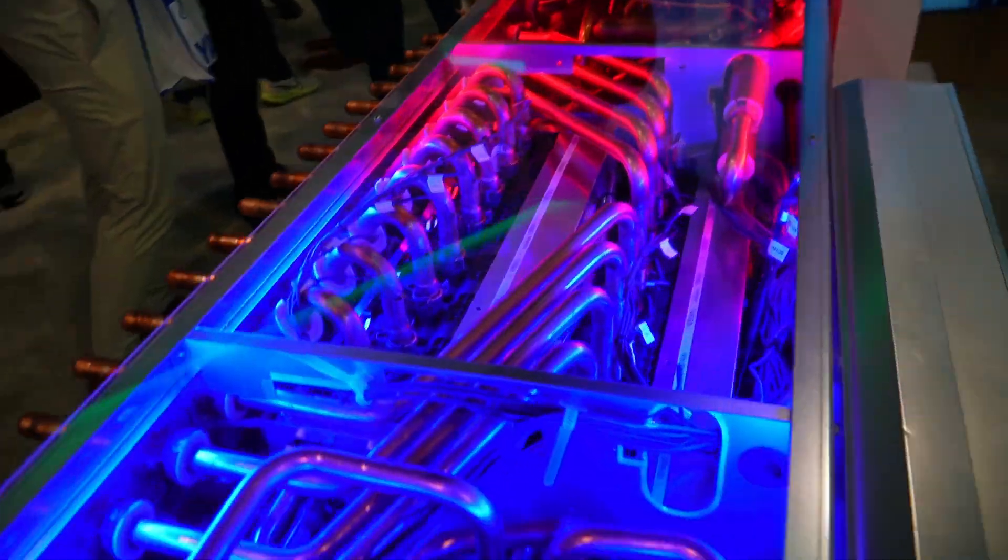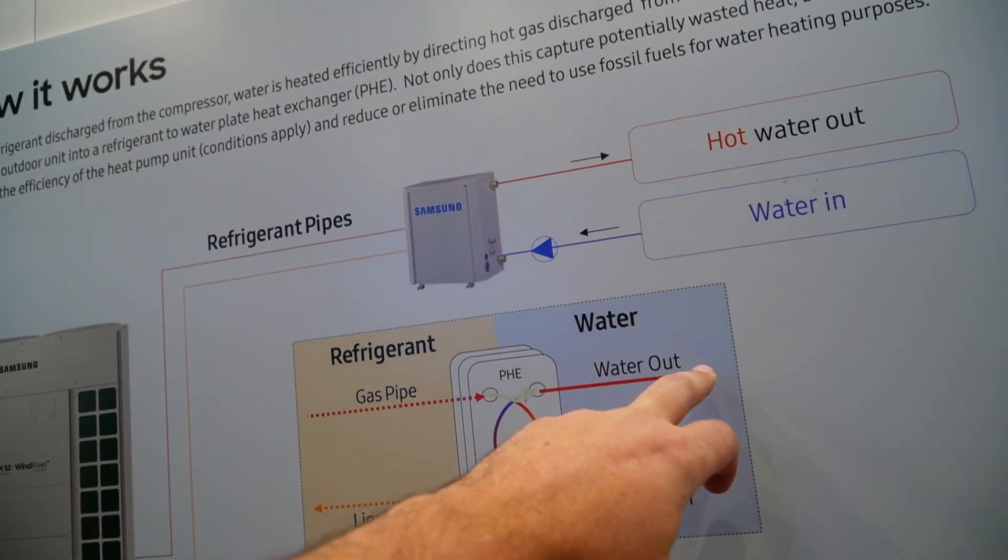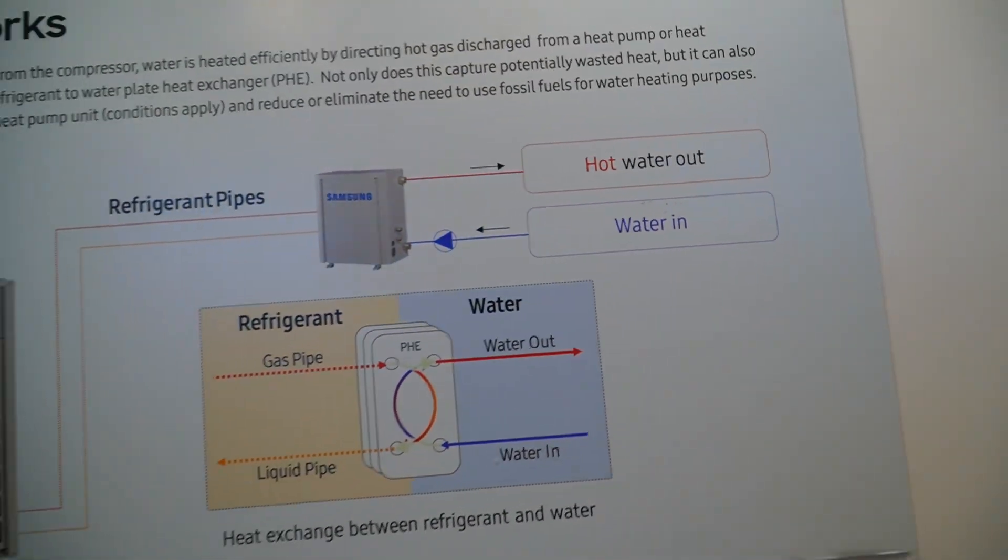This isn't just a regular branch selector — this is actually quite fascinating. They have integrated the hydronic system with a VRF branch controller. I did not know this existed. Don't think you've seen it all, because suddenly water and VRF start to mix. I already knew about water-cooled VRF on the Mitsubishi side, but it looks like now they're starting to tie in chilled water into the VRF and still have heating capacity through the heat pump side. Samsung is up to it too — they've got a VRF hydronic chiller. Welcome to the new world. I did not see VRF going this hard into integrating hydronics.